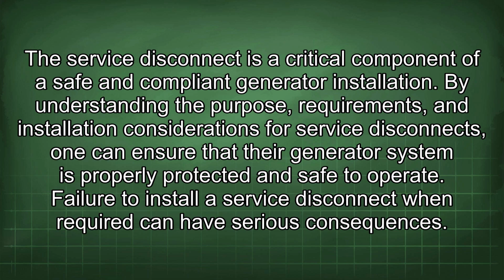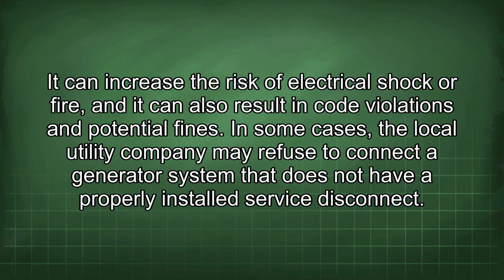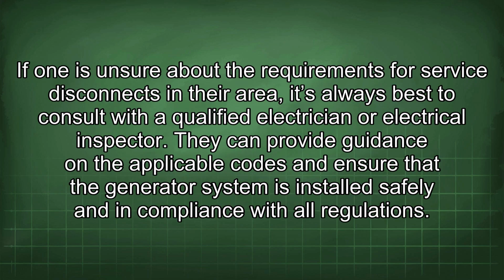Failure to install a service disconnect when required can have serious consequences. It can increase the risk of electrical shock or fire, and it can also result in code violations and potential fines. In some cases, the local utility company may refuse to connect a generator system that does not have a properly installed service disconnect. If one is unsure about the requirements for service disconnects in their area, it's always best to consult with a qualified electrician or electrical inspector. They can provide guidance on the applicable codes and ensure that the generator system is installed safely and in compliance with all regulations.